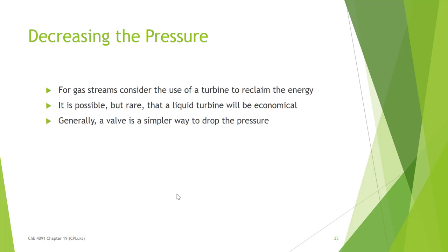When you need to decrease the pressure of a gas stream, look at using a turbine to reclaim the energy. It may not be cost effective — if you're not going to get enough energy reclaimed to justify the cost of the equipment, then just put in a simple valve. There are valve systems for large gas lines as well. For liquids, almost always a valve is going to be the simplest way to drop the pressure. It's possible you might use a liquid turbine to great effect, but generally we just put a valve in the line.